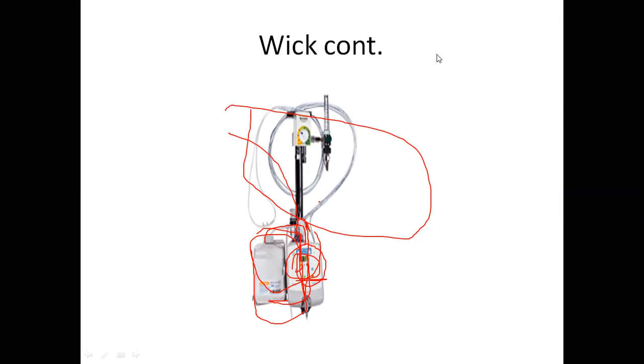So as far as wick continued, this is a high flow nasal cannula made by the same company, but I wanted to just show you the interface. That particular chamber that I showed you on the previous picture, it drops down through the middle of this. Here's your controls here to turn on the temperature and the temperature gradient so that you can control your relative humidity. There's that box of water. The top tube plugs into the top, the bottom tube plugs into the bottom. That circulates that water as that gas flows in one end and out the other. In this case, it's a high flow nasal cannula. So that is the Hudson wick device there.